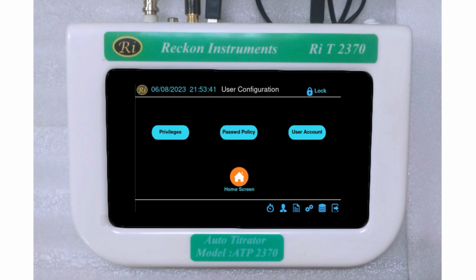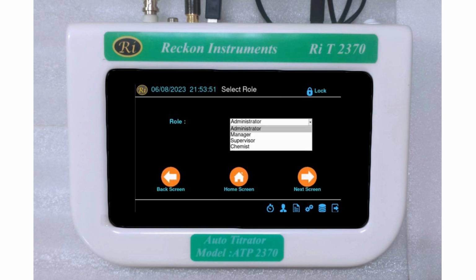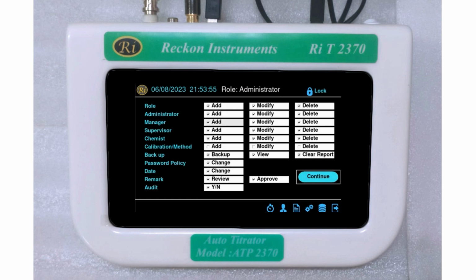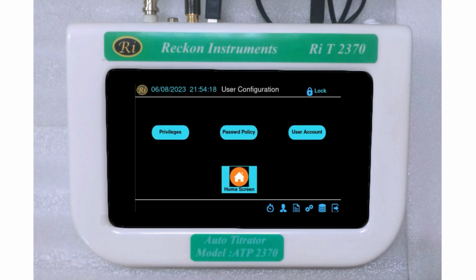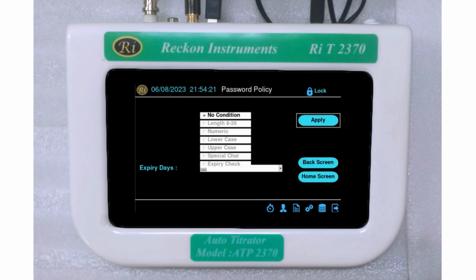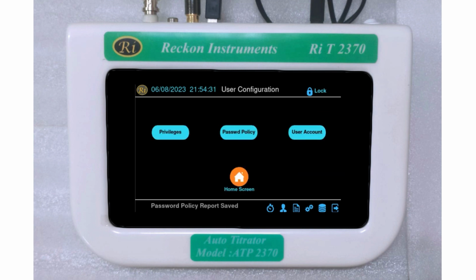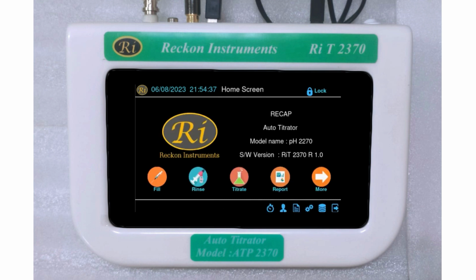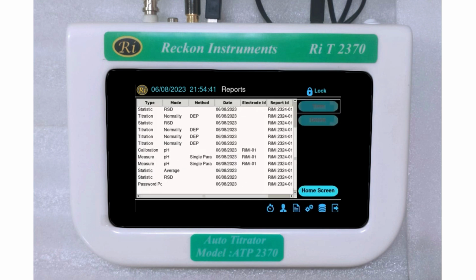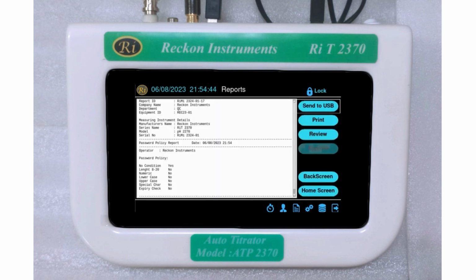As this is a 21 CFR Part 11 instrument, you have to configure it for user privileges, password policy and users. You can set the privileges for all the levels like administrator, manager, supervisor, chemist, and generate the privilege report. Set the password policy for length, capital letter, small letter, numeric letter, special character, expiry check, etc. After applying the password policy, a report for the same will be generated automatically.